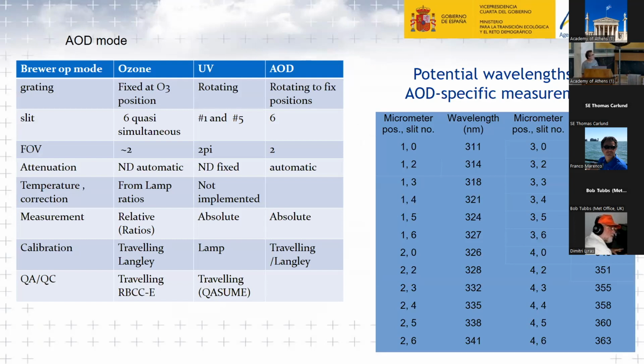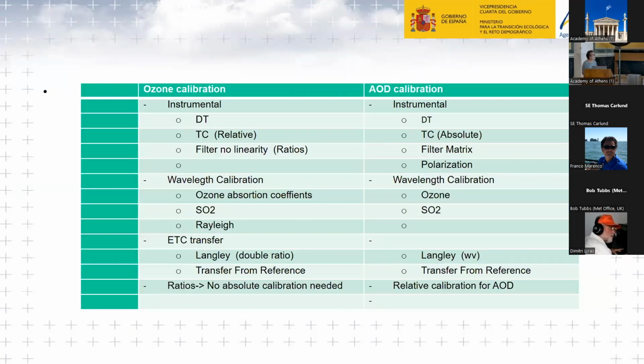In one mode of operation of the Brewer, used to measure ozone, the measurements are relative, we don't move the grating, and we have 6 quasi-simultaneous measurements. Instead, in the UV mode, we move the grating and scan all the wavelengths. In the AOD mode, we try to combine both methods, so we move the grating to certain positions but use the slit used for ozone. So we can have around 30 wavelengths, much faster than if we were scanning. We can use most of the ozone calibration for the AOD calibration.